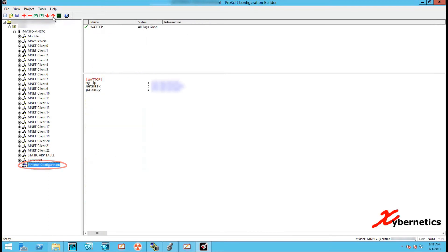To change your IP address of your ProSoft module, click on 'Ethernet Configuration on the tree on the left-hand side. This will bring up the edit WATTCP window. The first row is your IP address of your ProSoft module, the next is your subnet mask, and the last is the gateway. To change a value, highlight the row you want to change and modify each octet on the right-hand side, as I'm doing now for the IP address, subnet mask, and gateway.